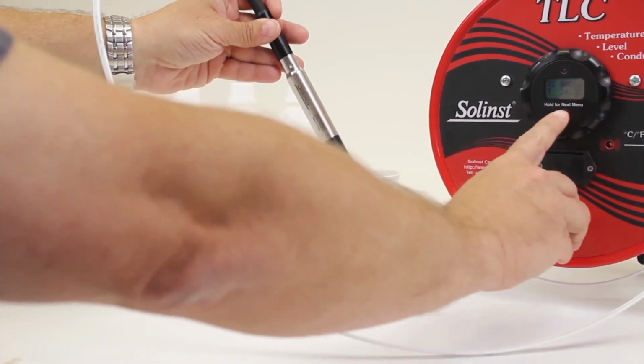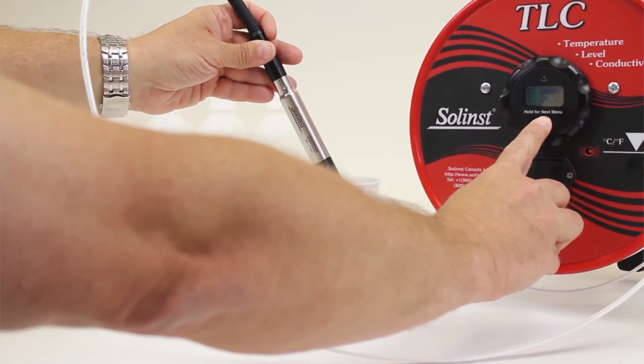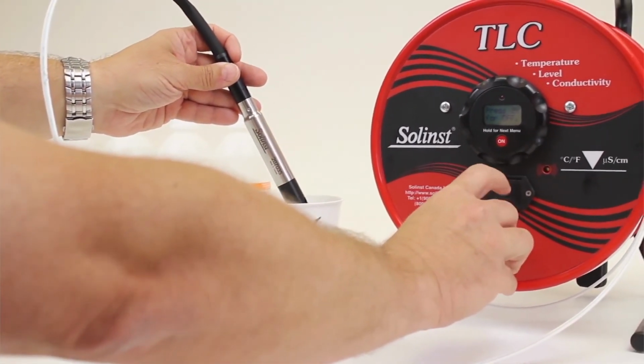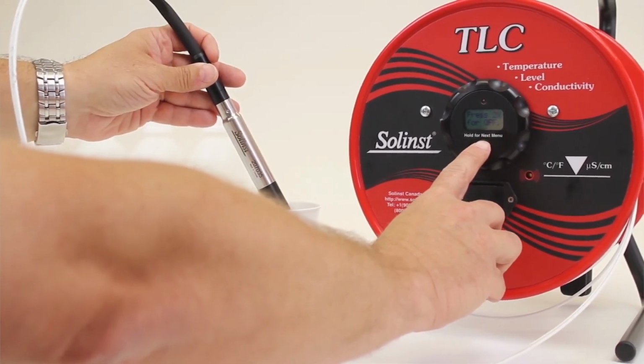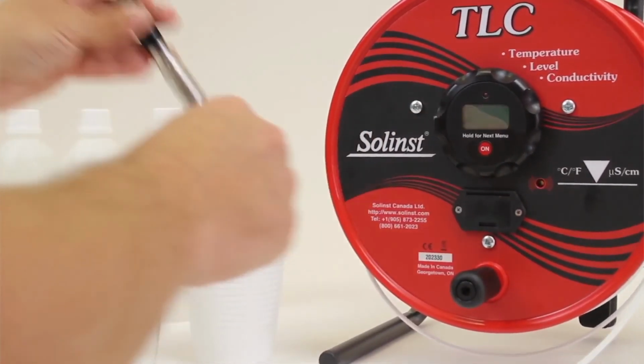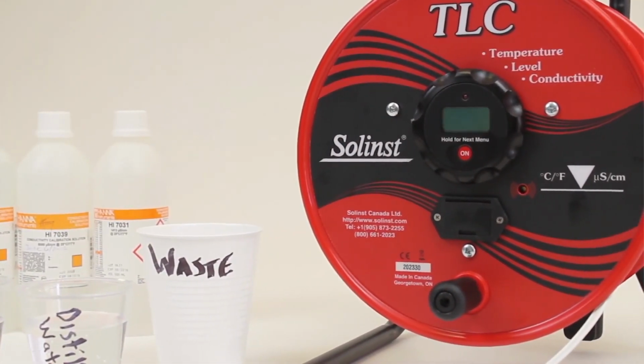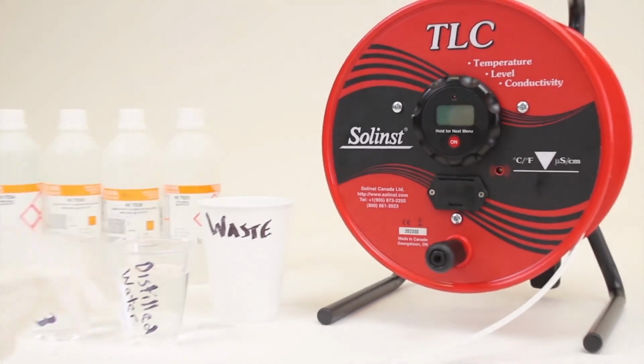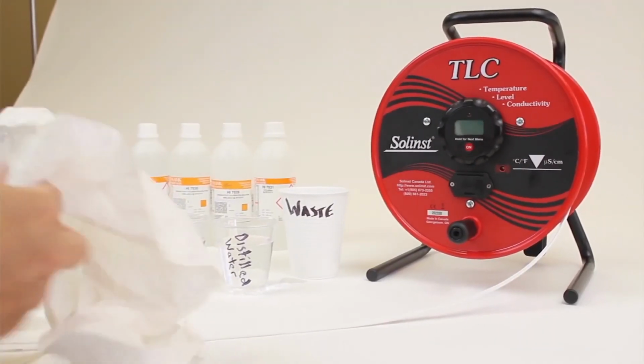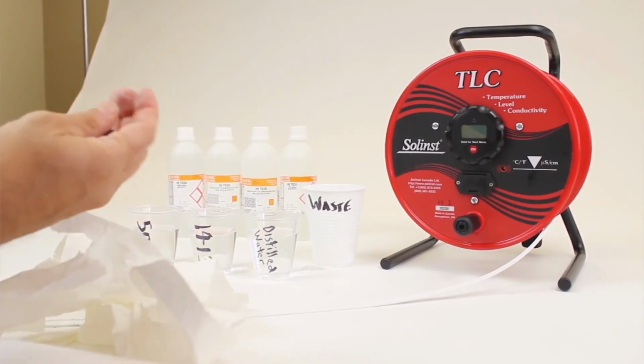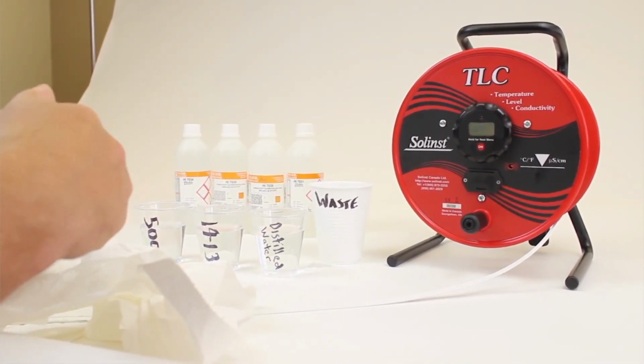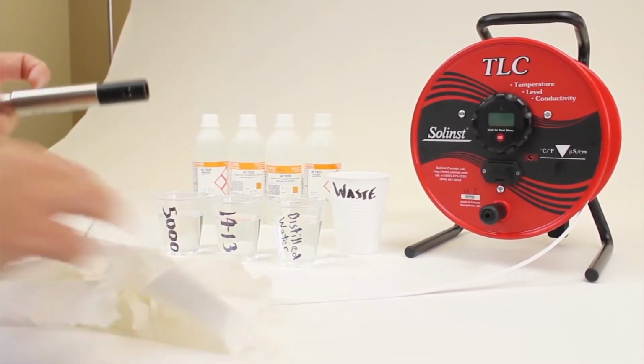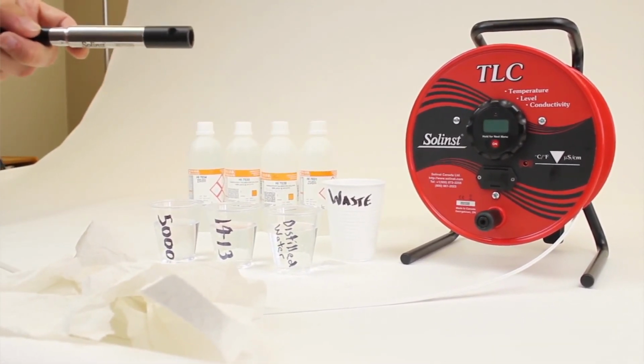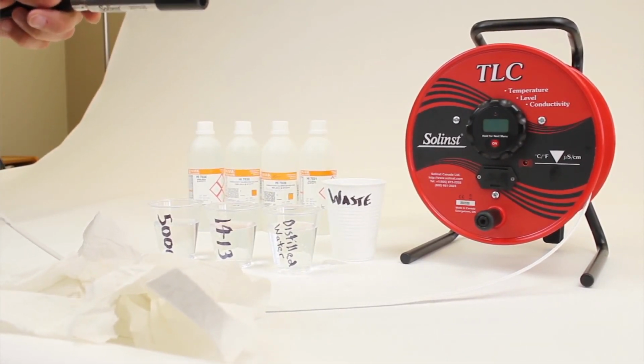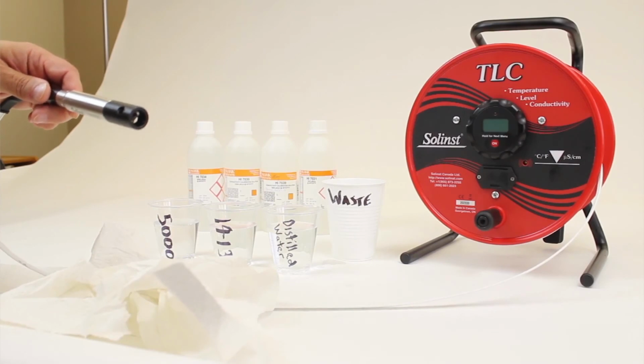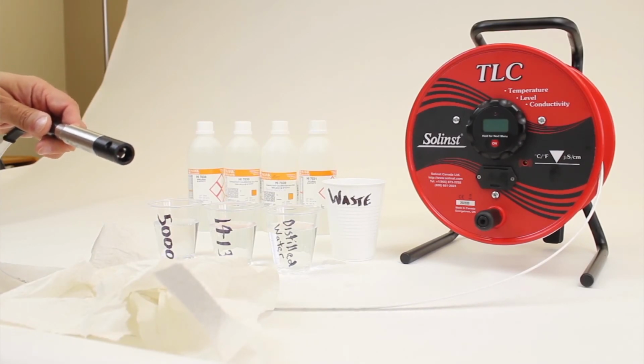I can turn the unit off by pressing and holding. Brings me to the screen where it says 2 times for off. Press it 2 times. Screen is done. I'll finish off by drying off the probe, taking the probe tip off again, just wiping it down, lining it up, pushing it together. Now I'm ready to go out to the field to take all my measurements, knowing I've got a nicely done user calibration that's going to give me accurate readings in the field.